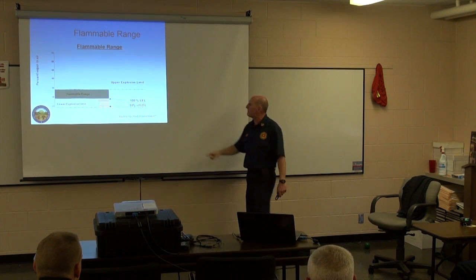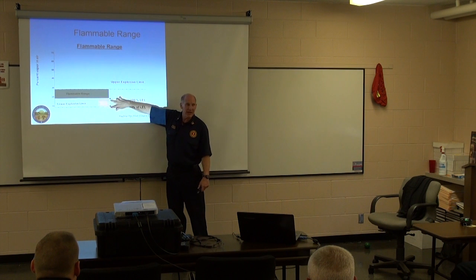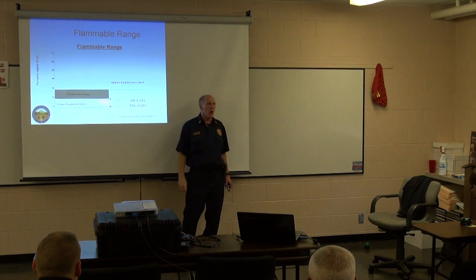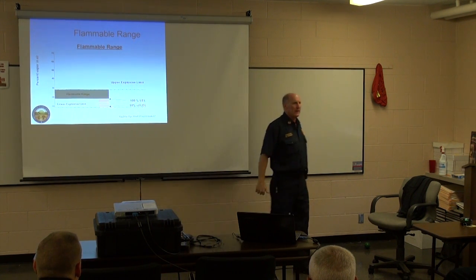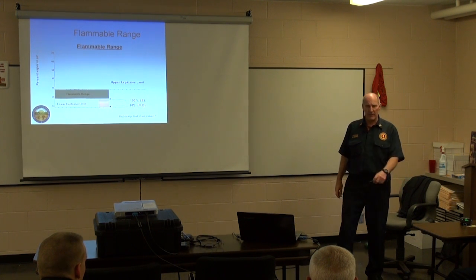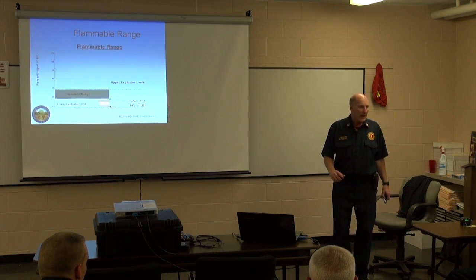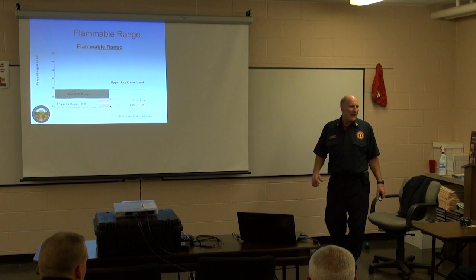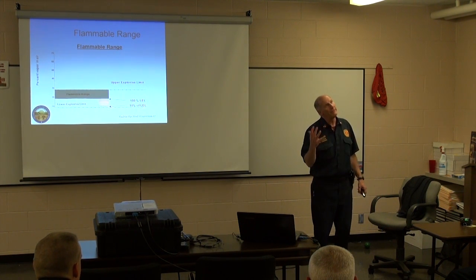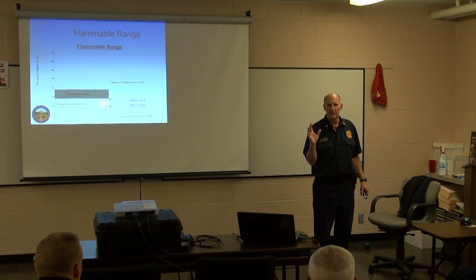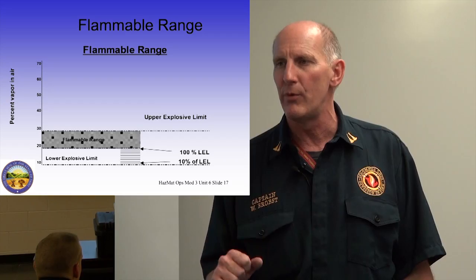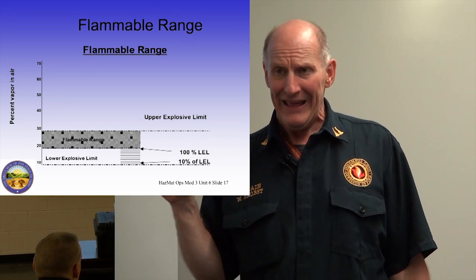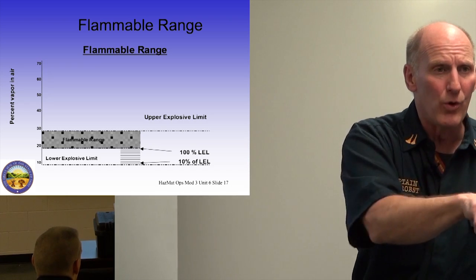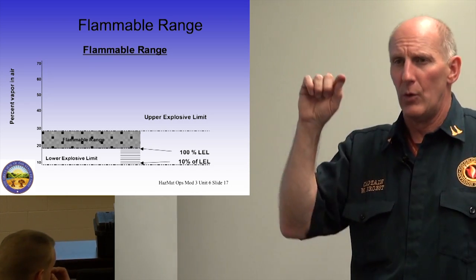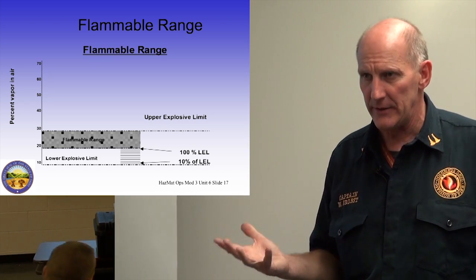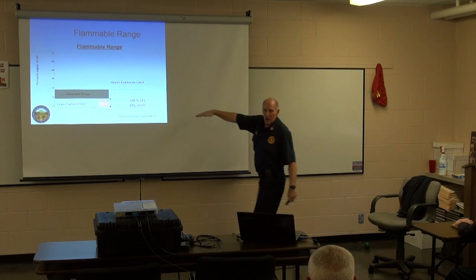So it measures a percentage of this LEL, and it is going to alarm at 10%. If, and let's hope I can get the mathematical formulas correct, if the LEL of methane is 1.4%, and don't trust me, the number's not important, it may not be 1.4%, then the alarm will go off at 0.14%. That's when the alarm goes off.